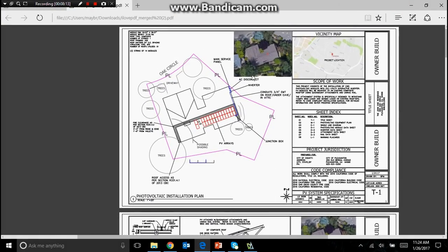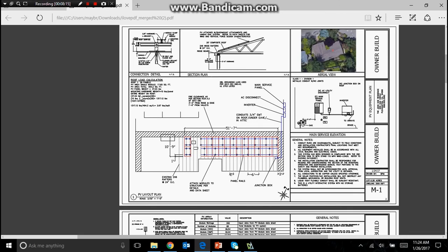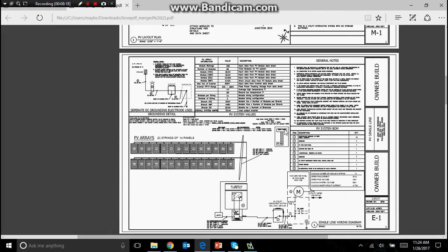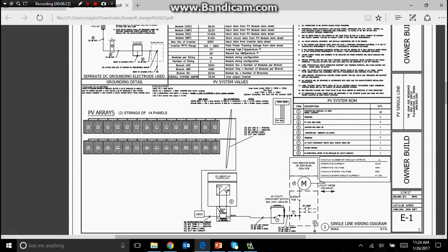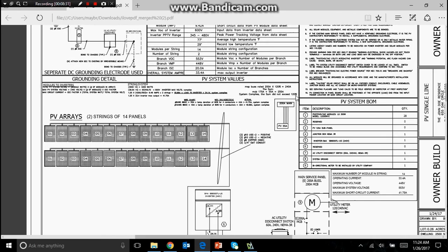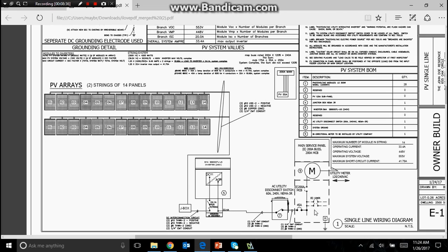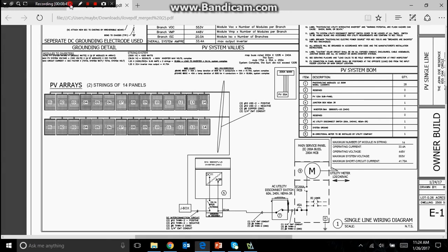I kind of did it on purpose, but there was one calculation you kind of want to view and go over. This is your peer review time, okay? There is one calculation that I did not do on purpose. I wanted to see if you guys caught it, and that is this one. This is the MSP bus, the main service panel bus rating. For this rating, it's rated 200 amps, as it says in our checklist here.